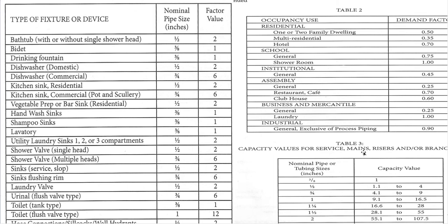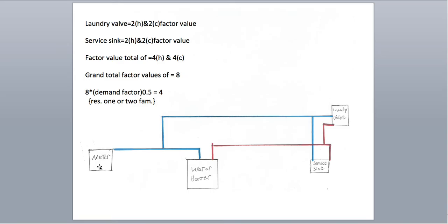Today we're going to do a real simple drawing just as a reminder or for beginners. Here we have a water meter, water heater, service sink, and laundry valve. Keep something in mind — you just have to orientate yourself. Everything on this hot line coming out of the water heater is going to have the factor values and the capacity of everything on the hot side. This leg into the water heater will be equal to this leg because everything on the hot side is on this cold leg. But at this T, you're going to have everything that's on the cold off this branch. And then off the meter, you're going to have both everything that's on the cold and everything that's on the hot.